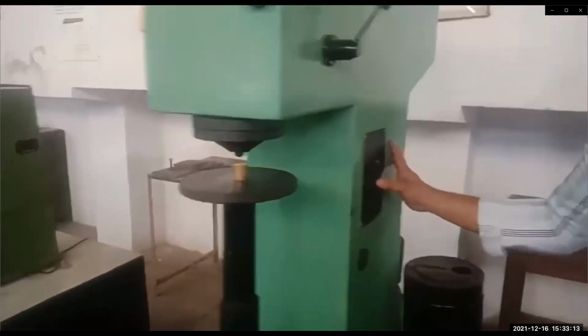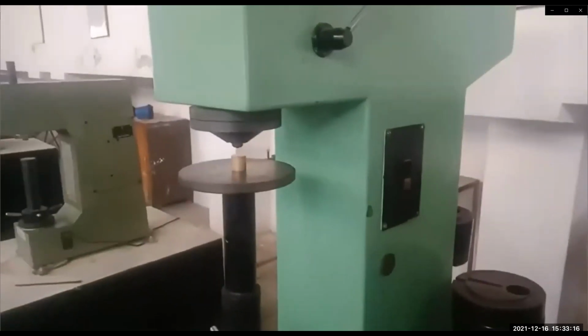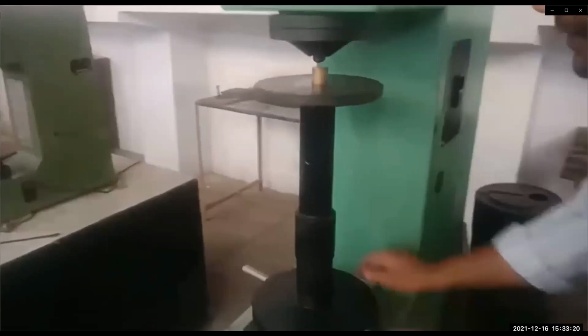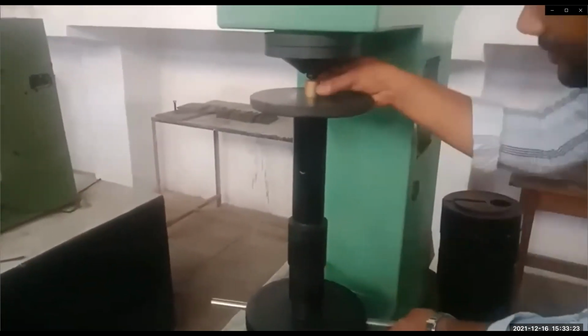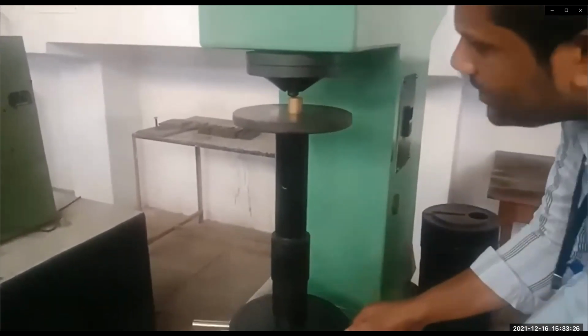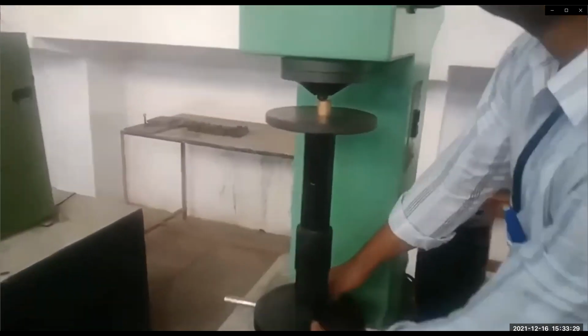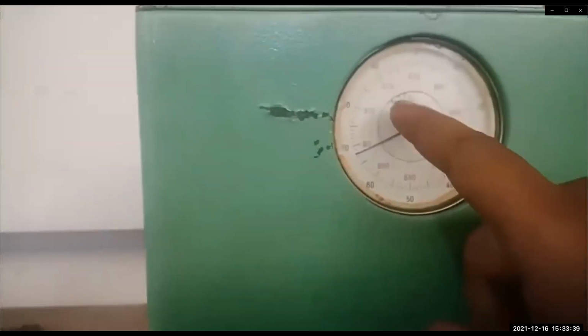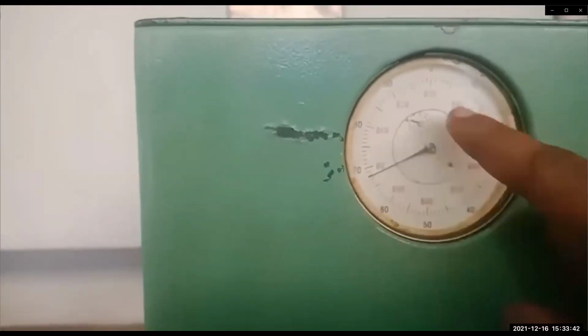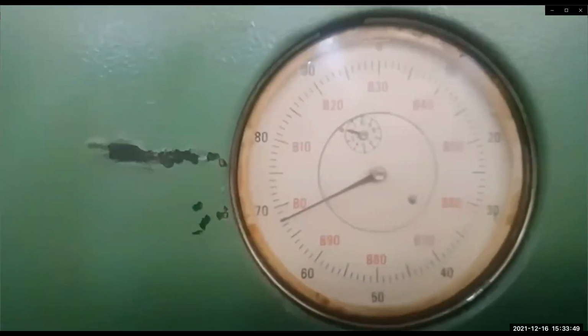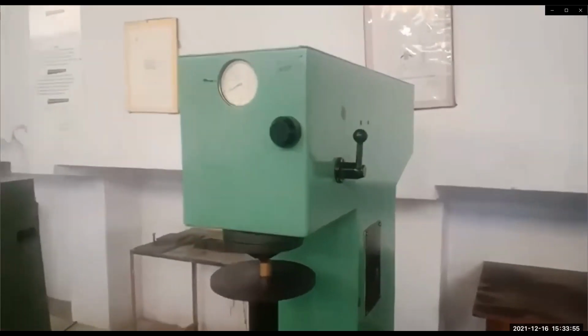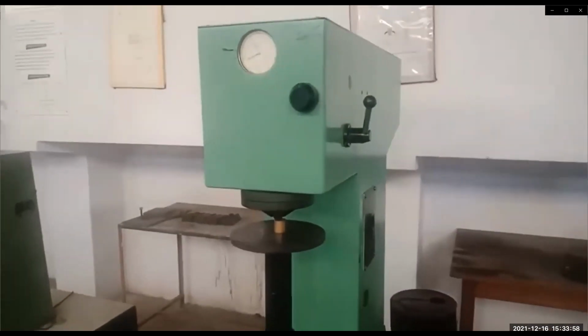Then switch on the machine. Once the machine is switched on, raise the anvil. Once it touches the indenter, the specimen, then I will set the minor load, I will rotate the anvil, and the smaller indicator will come slowly till it touches the red dot. The smaller needle in the smaller dial gauge touches the red dot, that means the minor load, that is the 10 kg, is acting on the specimen. Then slowly I will apply the load with the help of the load transfer lever.